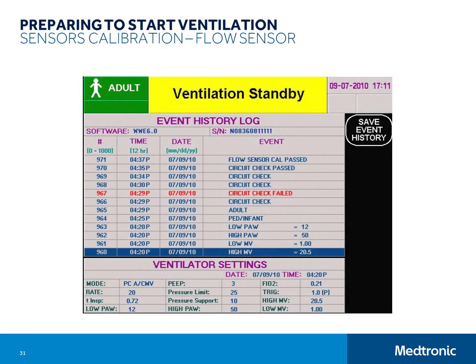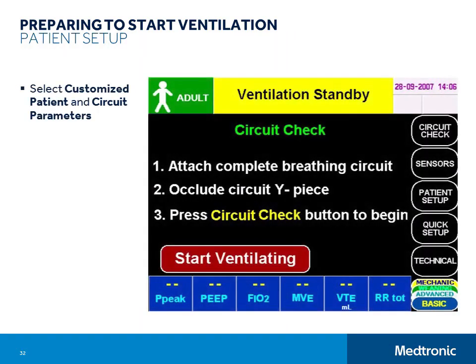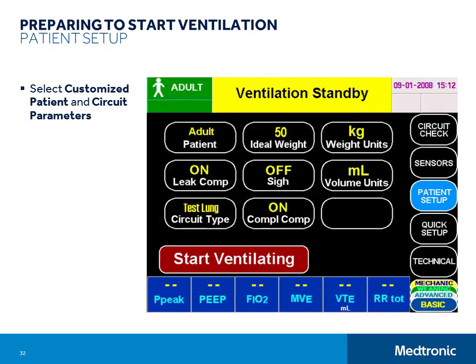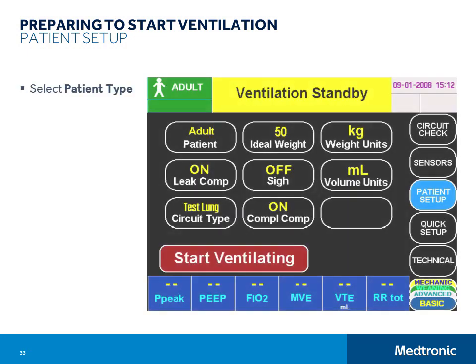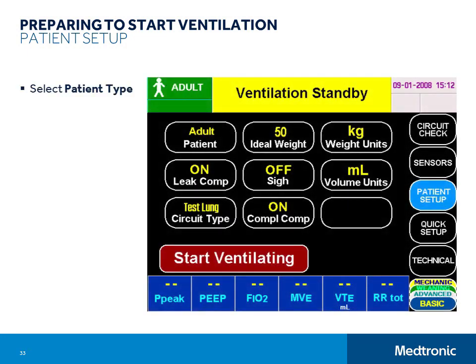The next step in preparing the e360 for patient use is to select the patient's setup parameters. From the Setup and Calibration menu, select Patient Setup. A new screen appears that allows you to customize patient settings. Patient setup parameters may be adjusted at any time while in standby or during ventilation. The first step is to select the patient type. The patient selection is indicated in the top left corner of the e360 status bar, so it is always visible when the ventilator is powered on.